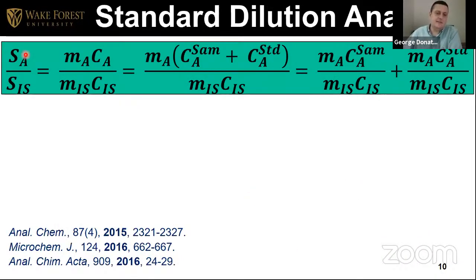So let's say you have the signal from the analyte and the signal from the internal standard. We take the ratio of those two. So the signal from the analyte is basically a sensitivity of the analyte times the concentration of the analyte. And the same thing for the internal standard. Now, the concentration of the analyte, because of the way the solutions work, you have signal coming from the sample itself and coming from the standard, because the way we prepare the solution with half sample, half standard, and the other one half sample too. So the concentrations here come from both.